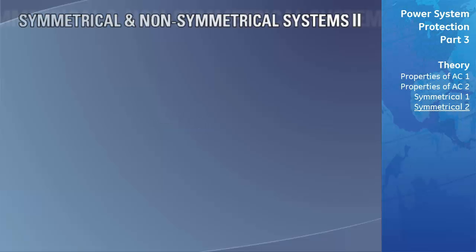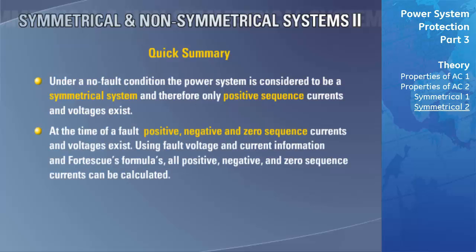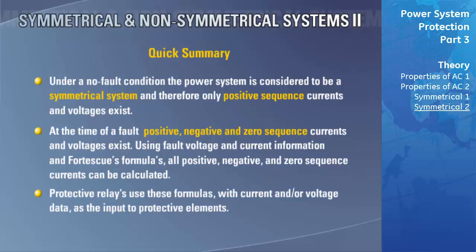To summarize: under a no-fault condition, the power system is considered symmetrical, and therefore only positive sequence currents and voltages exist. At the time of a fault, positive, negative, and zero sequence currents and voltages exist. Using real-world fault voltage and current information along with Fortescue's formulas, all positive, negative, and zero sequence currents can be calculated. The protective relay uses these formulas and real-world current or voltage data as input to protective elements. To understand Fortescue's formulas, we must first understand the A and A-squared operators.